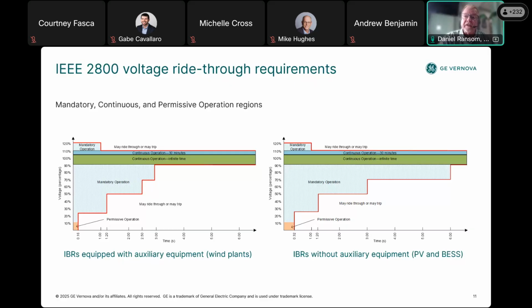And as you get down to a very small voltage, a big load or a heavy fault, that's the permissive operation range. Here it extends from 0.0 per unit to 0.1 per unit. In this area, the IBR can exchange current to the maximum current limit or operate in a current blocking mode, but it has to wait at least 0.16 seconds. That's 160 milliseconds as shown on the left for auxiliary equipment IBRs, and longer, 320 milliseconds as shown on the right for IBRs without auxiliary equipment. Those would be photovoltaic and battery energy storage systems.